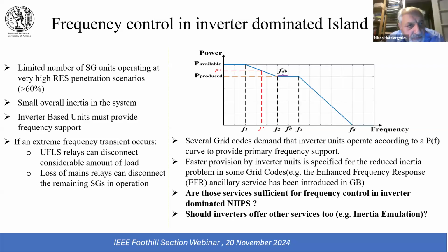In this system, as I said before, if you speak at the current levels of very high RES penetration scenarios, at least this is what is aimed today, I mean, very high RES, more than 60, 70% RES penetration, then you have the small overall inertia of the system. So the inverter-based units must provide frequency support. And when you have extreme frequency transients, then the frequency relays disconnect load, and the loss of mains relays can also disconnect the remaining synchronous generators.